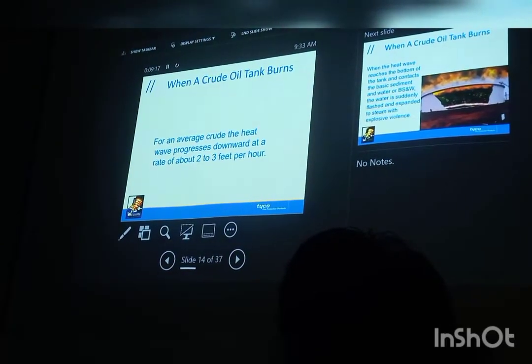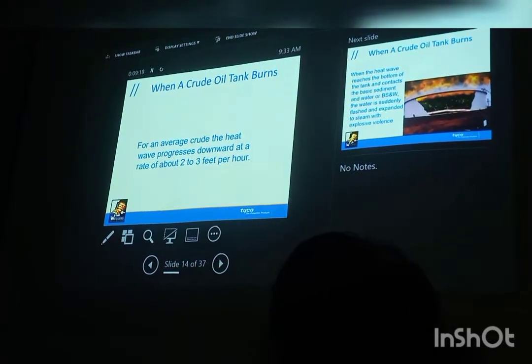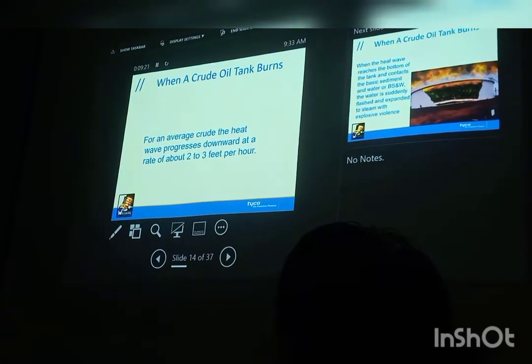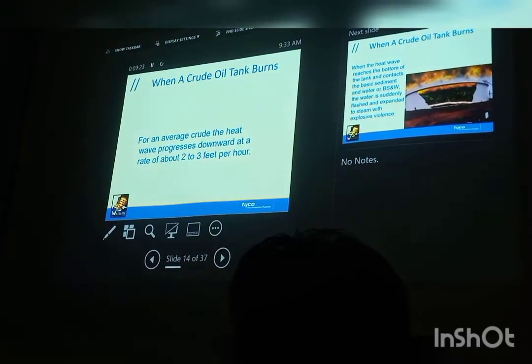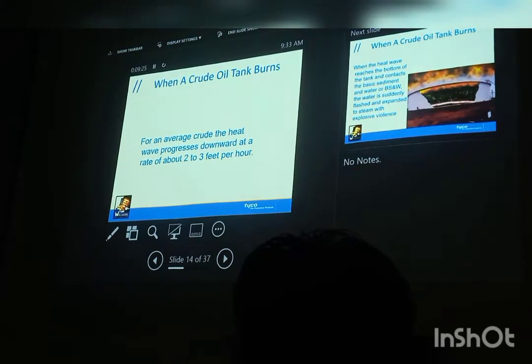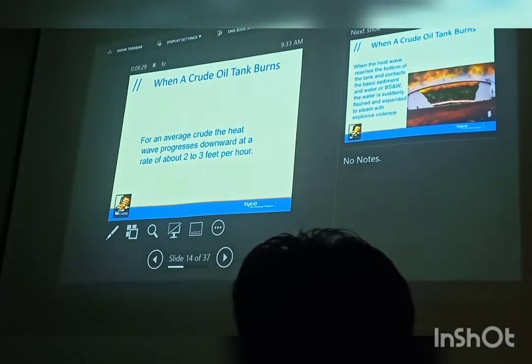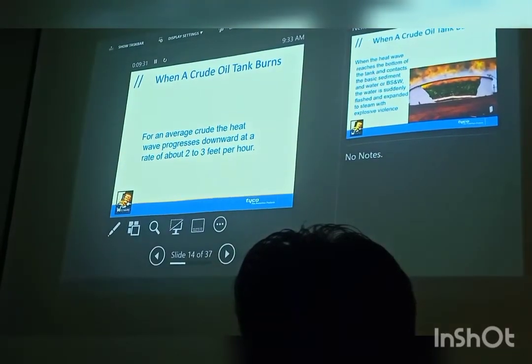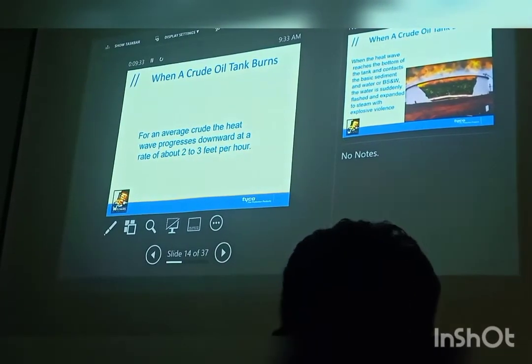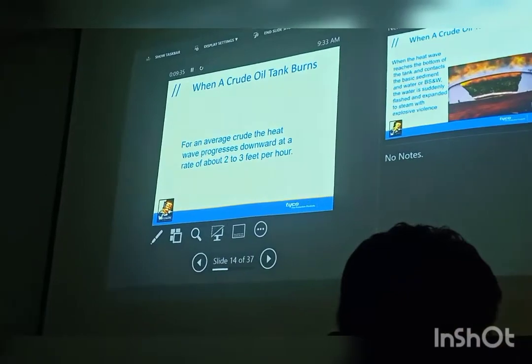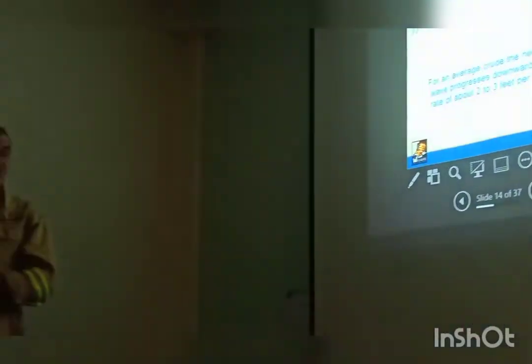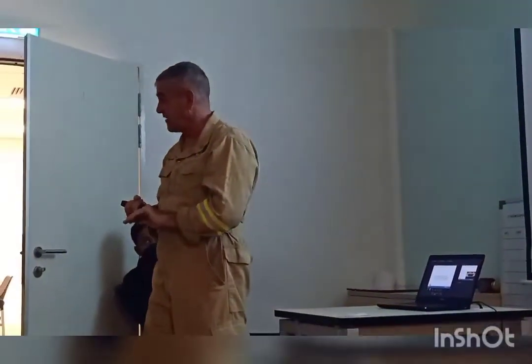22, right. And normally with that tank, are they keeping them full about 80%? 80%. Yeah, so about 80% of that. So what you're looking at is 80%. That's one of the first things we need to do. We're checking on the crude fire. We want to make sure the mixer is off. The second thing is we want to know what the level is in that tank.